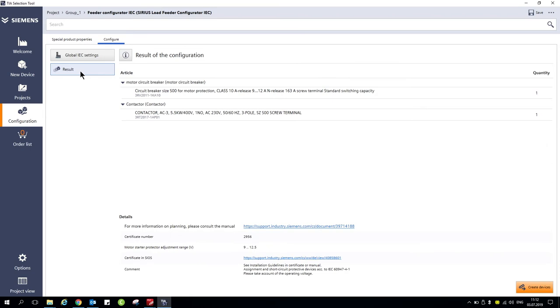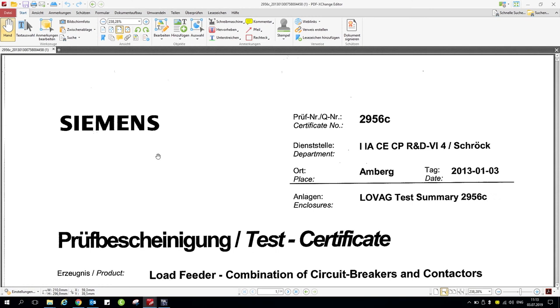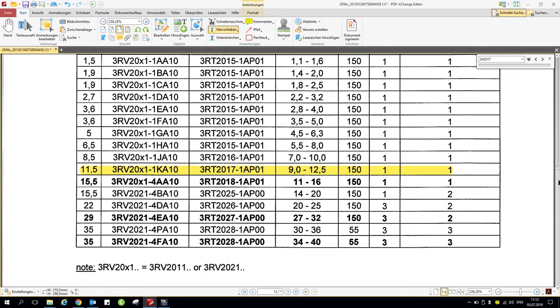In the result, we can see we have a circuit breaker and a contactor, and the details of the certificates are shown under them. If you click here, you will be prompted to Siemens Industry Online Support where you can view the certificates. After you download it, you can see the type-tested certificate. In the section marked, you see that this contactor, 3RT2017, has been tested with a 3RV21, which gives us 150kA — as was shown. Remember that this cannot be changed: this is a type-tested combination and no products within it can be substituted.